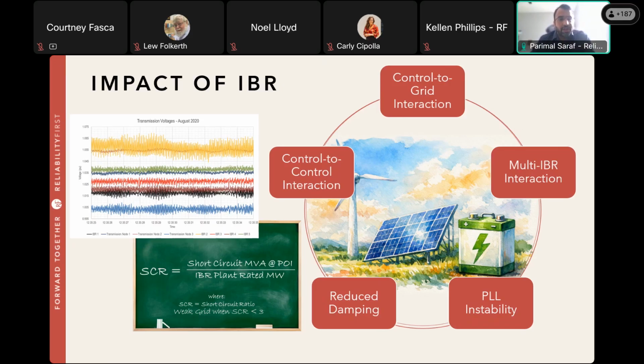The second phenomenon is control to grid interactions. In this type of phenomenon, there is essentially resonance between the grid impedance and the impedance of the IBR plant. Some of you might have already heard about a phenomenon named subsynchronous resonance or subsynchronous control interactions that are specific to IBR plants. So essentially, a resonance occurs between the grid and the IBR, and that results in oscillations being injected into the grid.